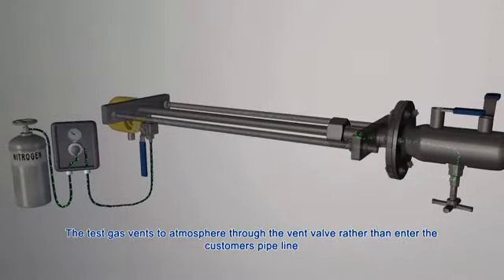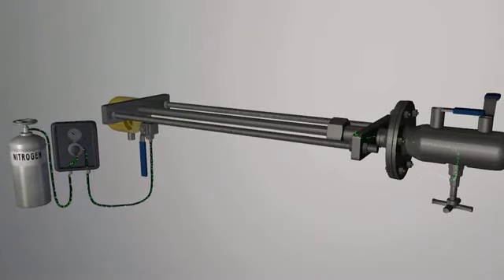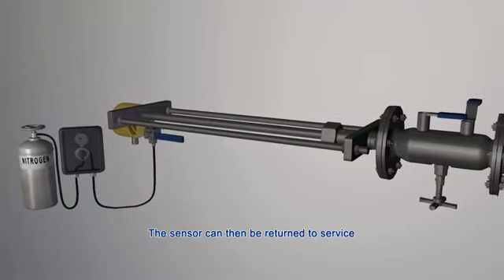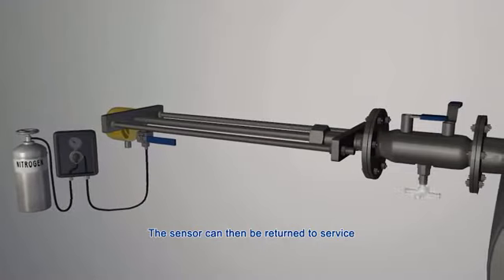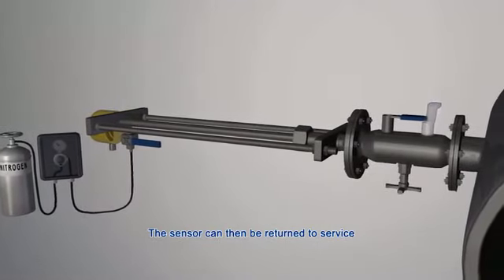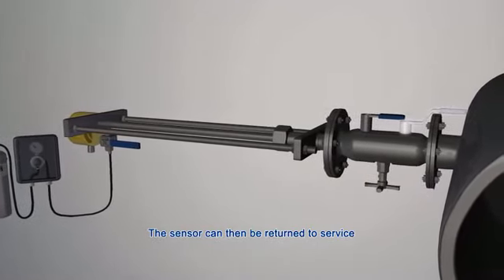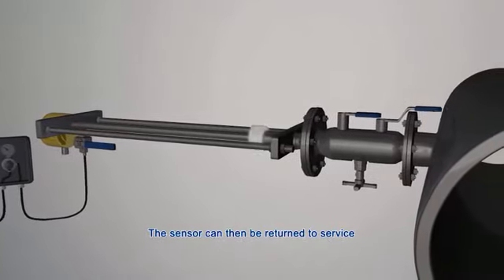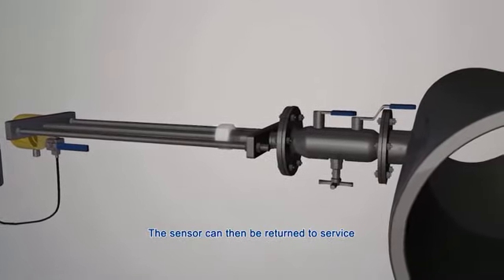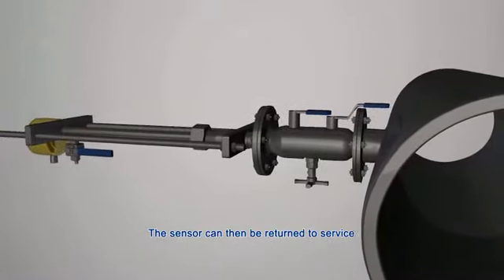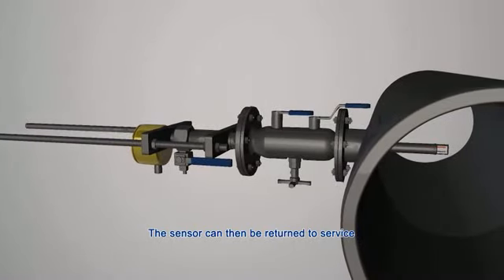The test gas vents to atmosphere through the vent valve rather than enter the customer's pipeline. The sensor can then be returned to service. The advantage of FCI's VeriCal system is that it provides on-site accuracy compliance without costly and time-consuming transportation of the Flowmeter to the factory for calibration recertification.